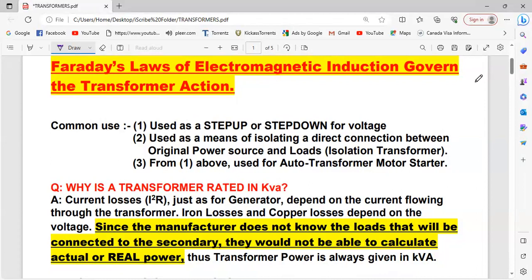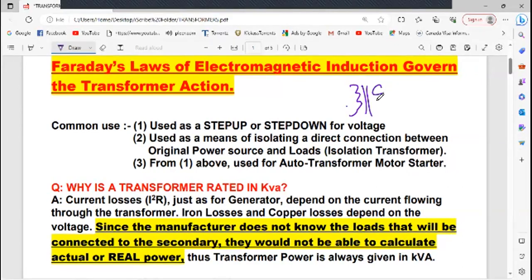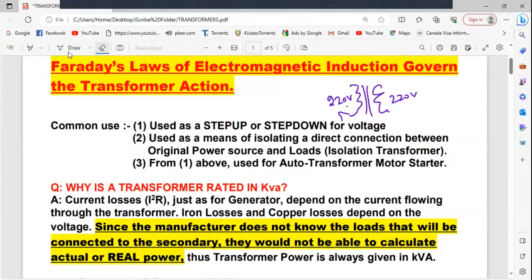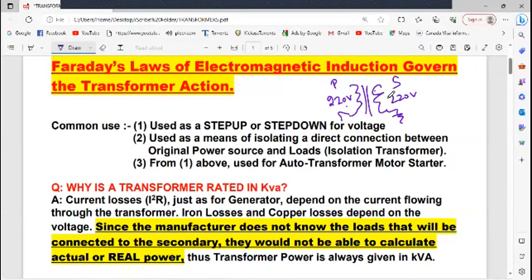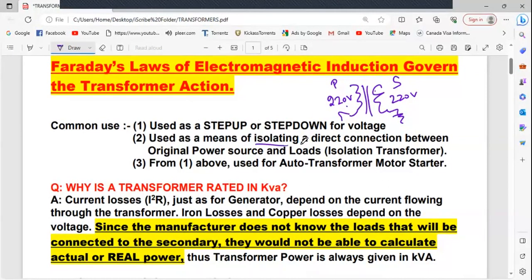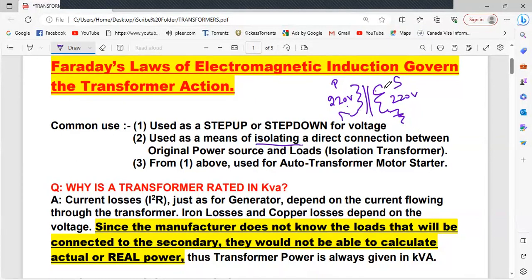So what do you do? Definitely we have some buffering transformers or isolating transformers. You'll have the same number of turns in the primary as in the secondary - so if it is 220 volts here, you will have 220 volts also here. But whatever earthing fault is in the secondary is not reflected into your primary. You have buffered it or isolated it. Such transformers are normally called isolating transformers, where your voltage and current are going to be the same in primary and secondary, so you can also use your secondary as a primary - you can interchange the connections and nothing is going to happen.